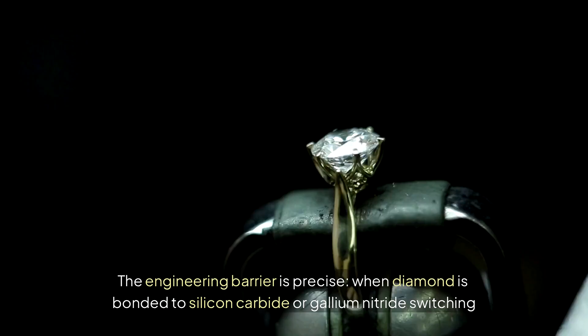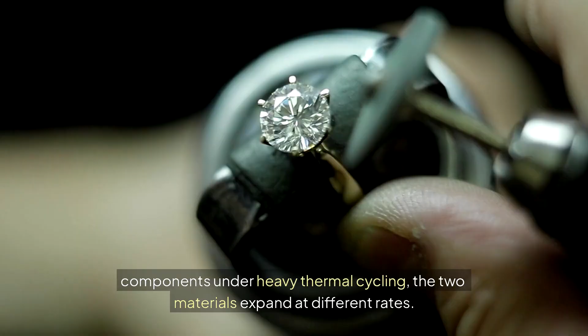The engineering barrier is precise. When diamond is bonded to silicon carbide or gallium nitride switching components under heavy thermal cycling, the two materials expand at different rates. The mechanical shear stress at the boundary cracks the diamond's thermal pathway. Until that interface problem is solved, the grid bypass stays in the laboratory.